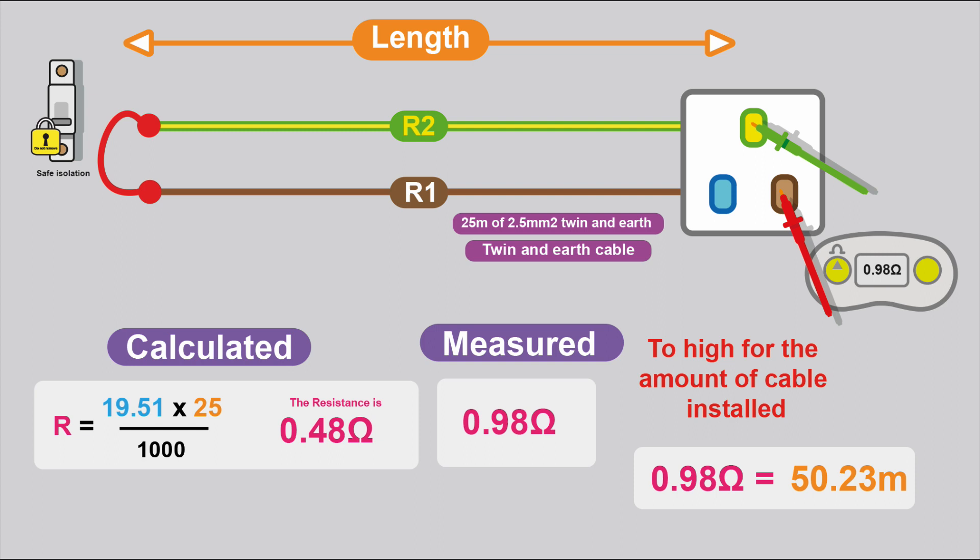That's why it's such a useful test. You're making sure that the circuit is installed correctly before you're livening it up. It's also useful for when you're doing your periodic inspection, because you can verify your results against the length of the circuit.